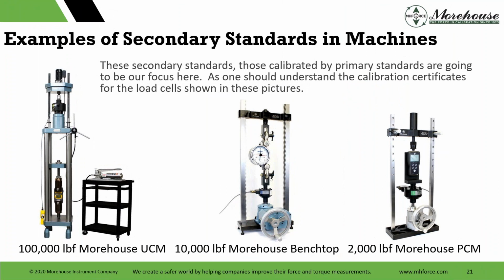As one should understand, the calibration certificates for the load cells are shown in the pictures. Here we have 100,000 UCM. There's the reference standard, should be calibrated by primary. Here, interesting, we have our bench top, a 10,000 pound bench top. Depending on what the use is, this could be calibrated by secondary in the UCM, or it could be calibrated by primary.